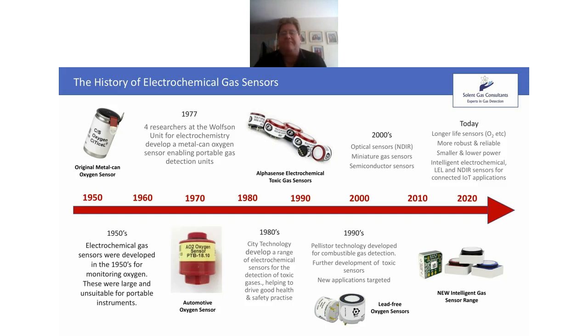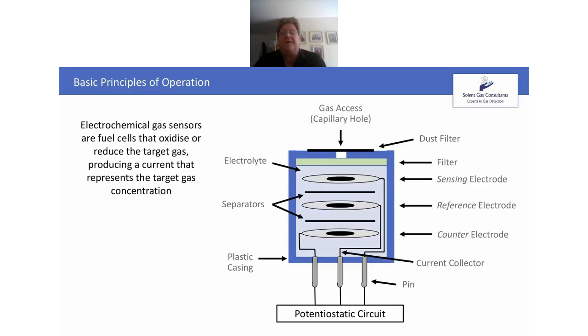How can I move forward? So, just a bit about how the sensors work. Basically, electrochemical gas sensors, they're fuel cells. The gas enters the sensor through a capillary hole, and that gas is either reduced or more commonly oxidized at an electrode. This produces an electric current proportional to the gas concentration.